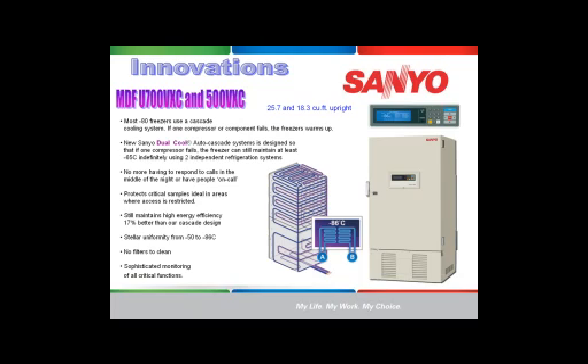The majority of ultra-low freezers on the market use a cascade system where one compressor cools the next. So the disadvantage of that is that if one compressor fails or one component in that system fails, the freezer warms up. If you're not getting cooling on either compressor, that freezer will warm up to room temperature eventually. Our new DualCool freezers, our MDF U700VXC and 500VXC, offer two completely independent refrigeration systems in the same freezer.